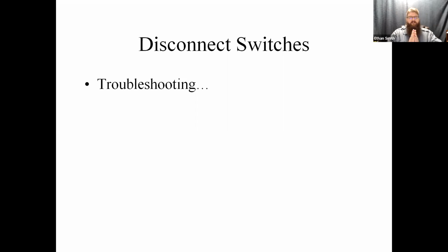Okay, here's the trick. Fuses are switches. That's all they are. The trick is they're a switch that only works once. So we can test fuses the same way we test switches. A good fuse will have no voltage drop across it. A bad fuse will.